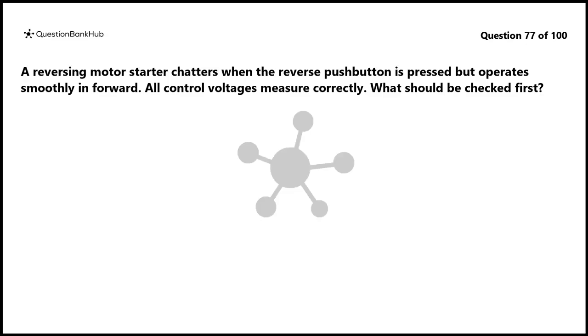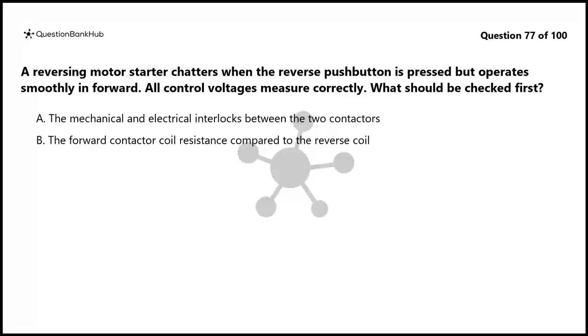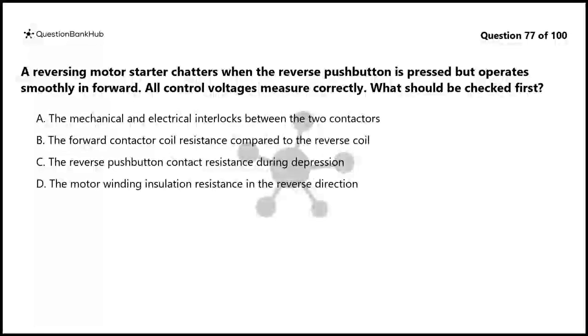Question 77. A reversing motor starter chatters when the reverse push button is pressed but operates smoothly in forward. All control voltages measure correctly. What should be checked first? A. The mechanical and electrical interlocks between the two contactors. B. The forward contactor coil resistance compared to the reverse coil. C. The reverse push button contact resistance during depression. D. The motor winding insulation resistance in the reverse direction.